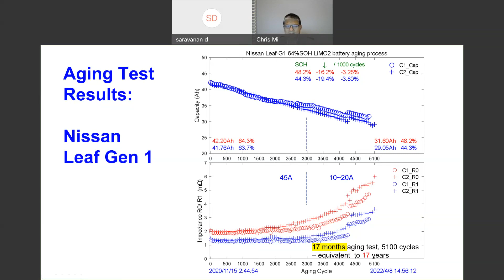The Gen 3 battery test result is quite dramatic. As you can see from the top graph, some of the batteries in the second life show aging knee around 1,000 cycles. Other batteries show aging knee around 1,900 to 2,000 cycles.